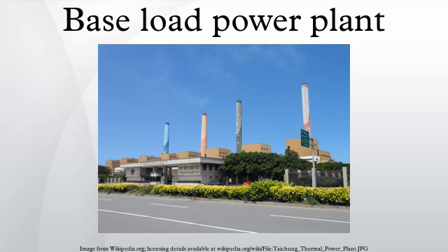Each baseload power plant on a grid is allotted a specific amount of the baseload power demand to handle. The baseload power is determined by the load duration curve of the system. For a typical power system, the rule of thumb is that the baseload power is usually 35 to 40% of the maximum load during the year.